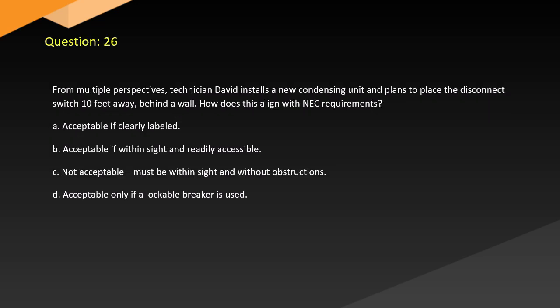Question 26. From multiple perspectives, technician David installs a new condensing unit and plans to place the disconnect switch 10 feet away, behind a wall. How does this align with NEC requirements? A. Acceptable if clearly labeled. B. Acceptable if within sight and readily accessible. C. Not acceptable. Must be within sight and without obstructions. D. Acceptable only if lockable breaker is used.